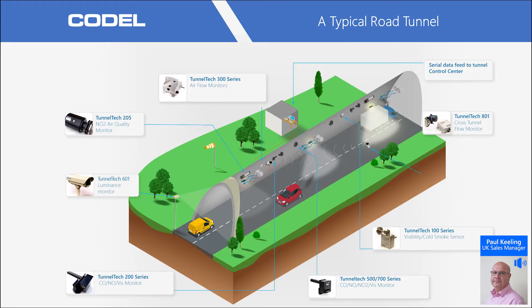Starting at the top left with gas measurement — basically you've got gas analysers measuring CO, NO, NO2, and even SO2. We have luminance sensors, illuminance sensors, and different kinds of sensors. The gas sensors can be single gas, combined, infrared, or electrochemical cell in nature. Visibility is also measured here — this is an opacity-mode measurement, referred to as smoke or opacity in this application — relating to the particulates mentioned earlier. It can be combined with certain gas sensors for easy installation or be a standalone device.